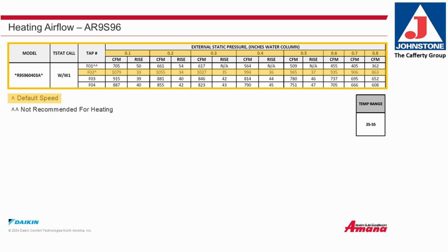For instance, at the default fan speed, at 0.1 inches of water column static pressure, the CFM is 1079 with a temperature rise of 33 degrees. At 0.5 inches of water column, the CFM is 965 with a temperature rise of 37 degrees.